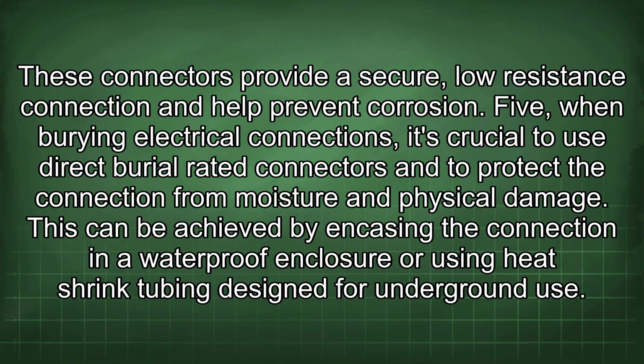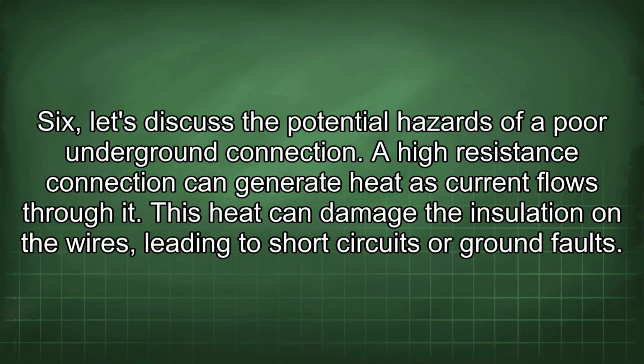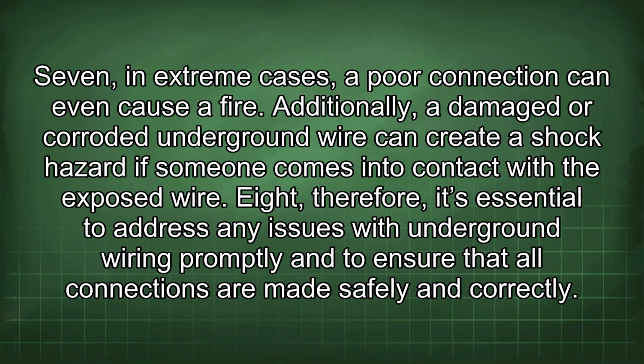5. When burying electrical connections, it's crucial to use direct burial-rated connectors and to protect the connection from moisture and physical damage. This can be achieved by encasing the connection in a waterproof enclosure or using heat shrink tubing designed for underground use. 6. Let's discuss the potential hazards of a poor underground connection. A high-resistance connection can generate heat as current flows through it. This heat can damage the insulation on the wires, leading to short circuits or ground faults. 7. In extreme cases, a poor connection can even cause a fire.